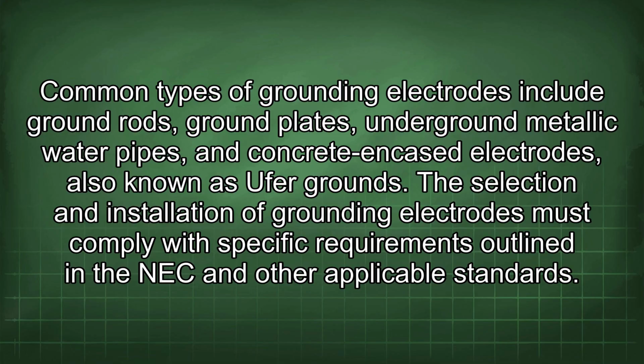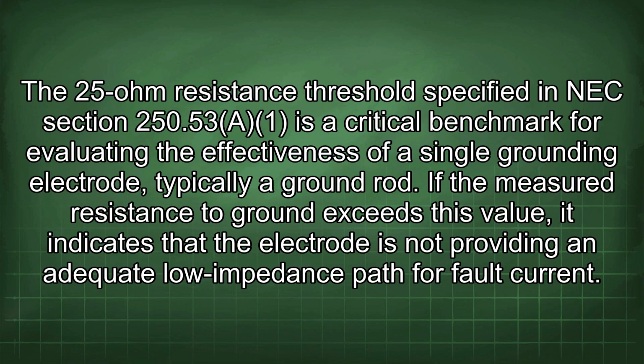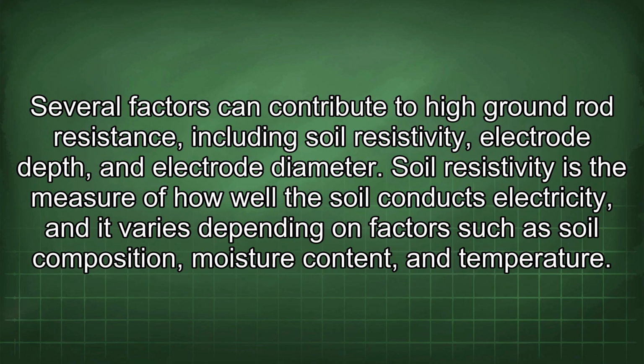The 25 ohm resistance threshold specified in NEC section 250.53 is a critical benchmark for evaluating the effectiveness of a single grounding electrode, typically a ground rod. If the measured resistance to ground exceeds this value, it indicates that the electrode is not providing an adequate low impedance path for fault current. Several factors can contribute to high ground rod resistance, including soil resistivity, electrode depth, and electrode diameter.